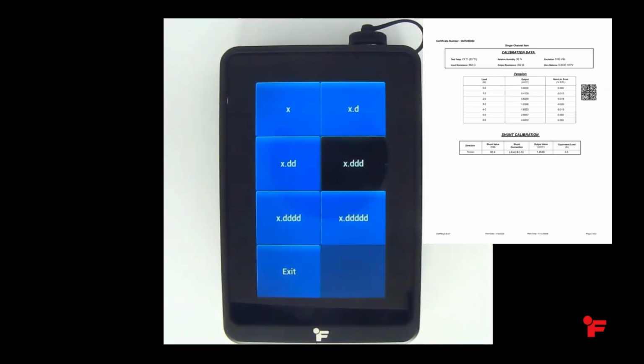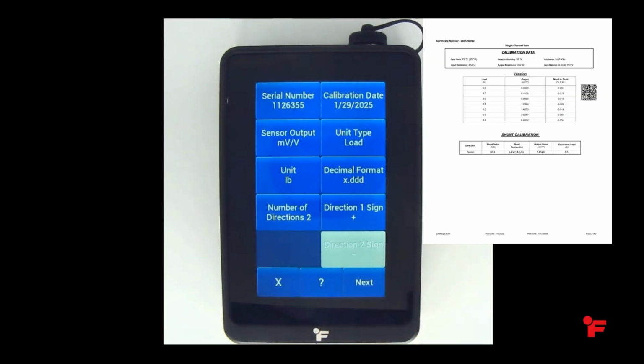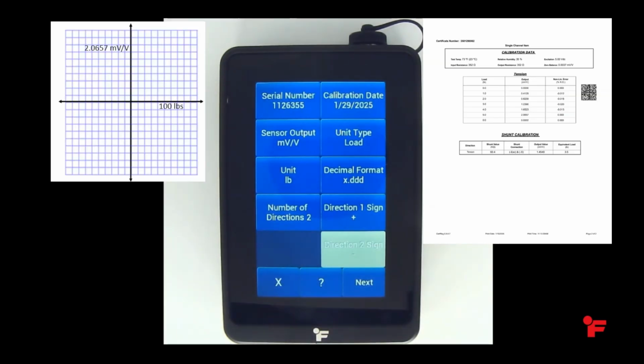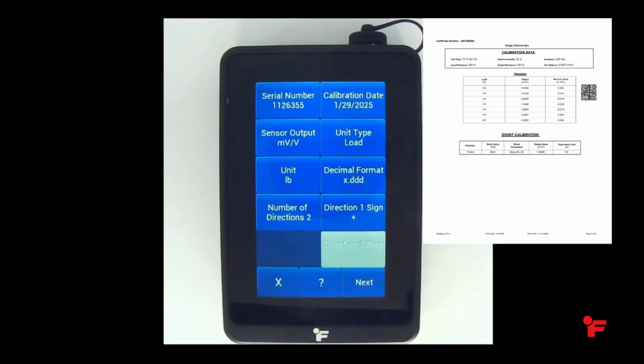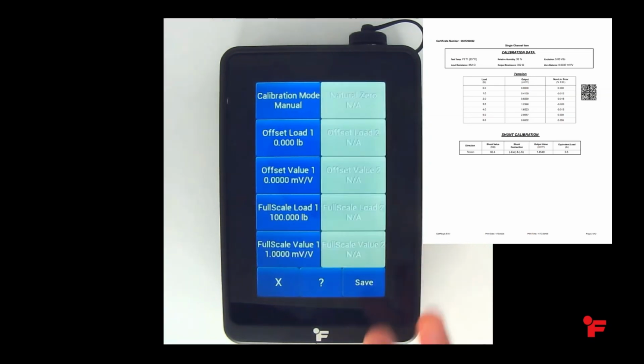The decimal format is a fixed decimal place setting. Using one direction calibration information means the instrument will apply the curve that it has for that one direction to the opposite direction as well. Using two directions means that the instrument can compensate for any symmetry differences between one direction and the other. The calibration information is for one direction only, so we will set number of directions to 1.